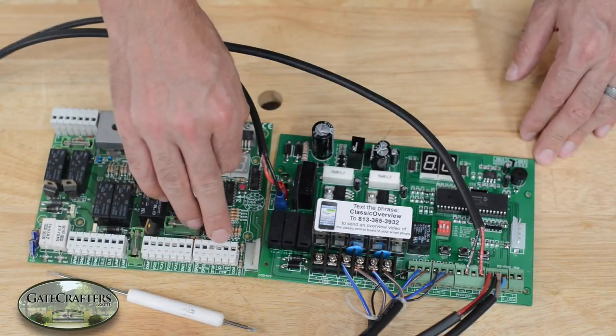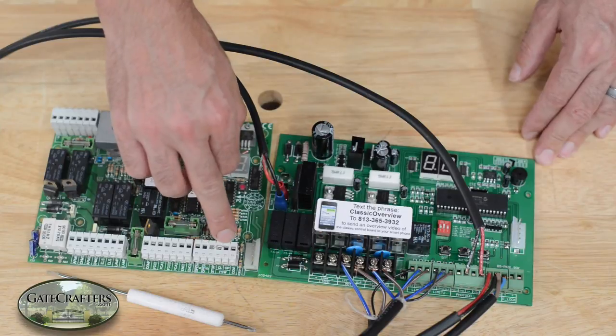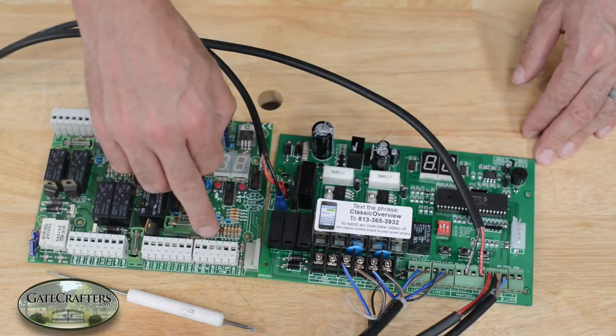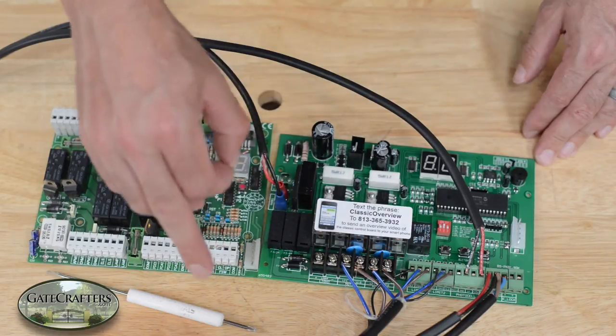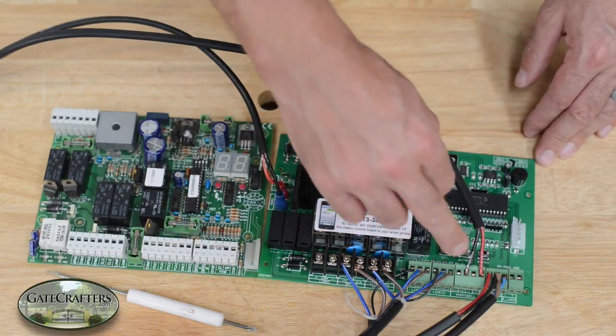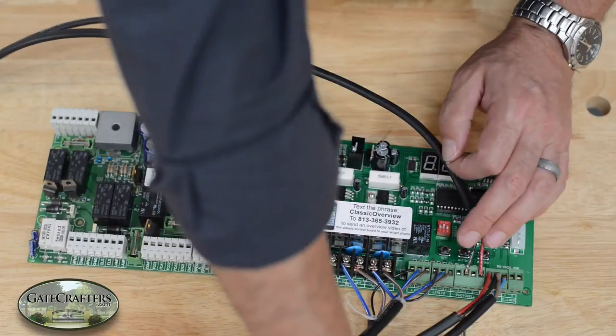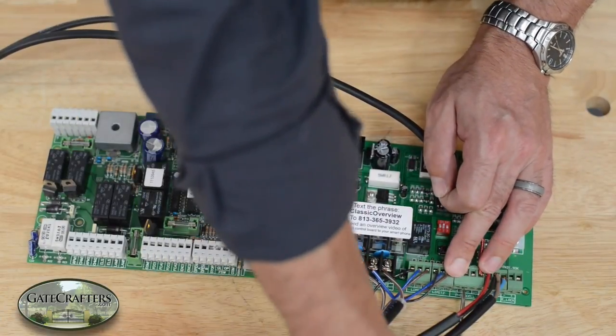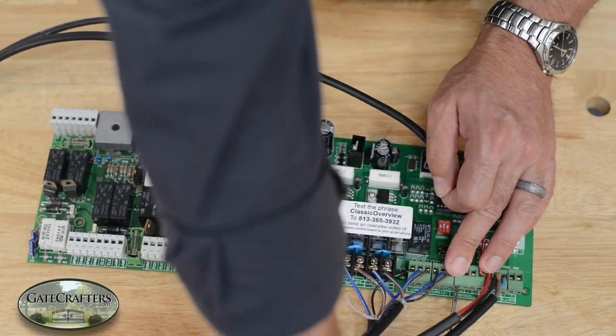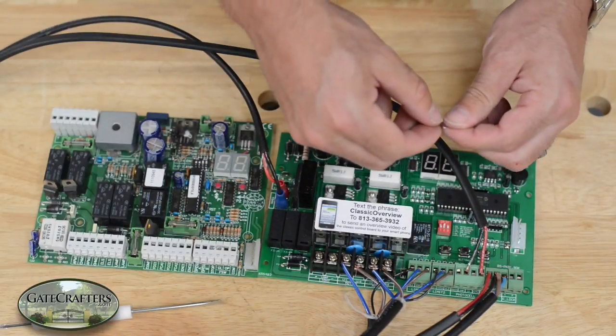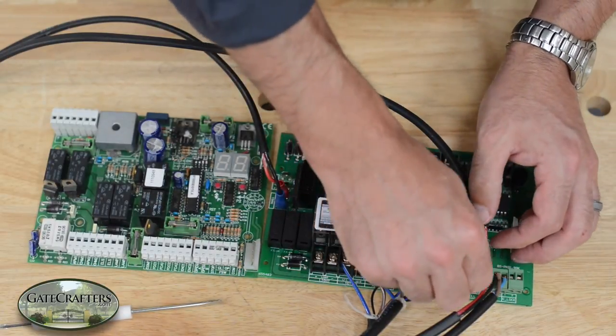If you have a photo cell, you should have a wire in one or two or all three of these terminals and a common. And you'll take the wire that's in all those terminals, condense it into one, and put it in the same place I'm putting the jumper. You'll notice I'm loosening the ground because I'm going to put the jumper from photo to ground.